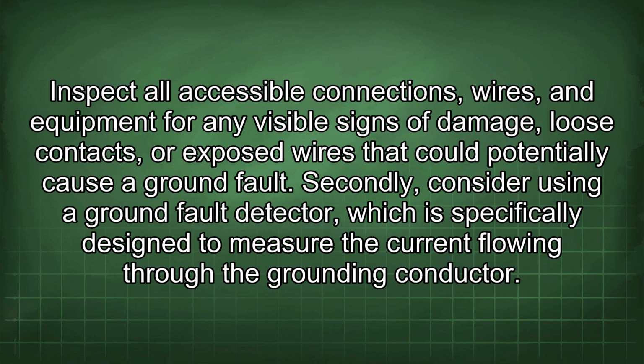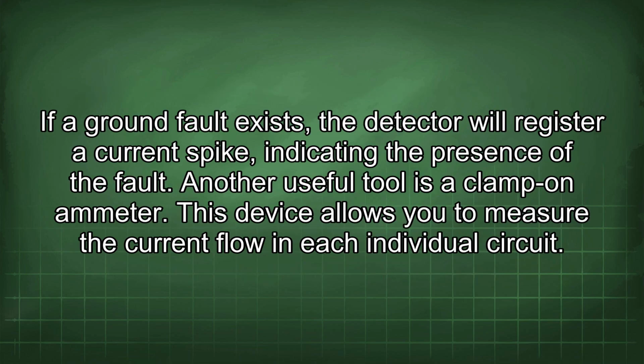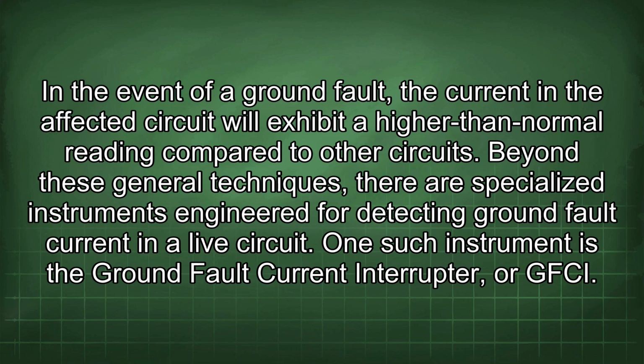Secondly, consider using a ground fault detector, which is specifically designed to measure the current flowing through the grounding conductor. If a ground fault exists, the detector will register a current spike indicating the presence of the fault. Another useful tool is a clamp-on ammeter. This device allows you to measure the current flow in each individual circuit. In the event of a ground fault, the current in the affected circuit will exhibit a higher than normal reading compared to other circuits.